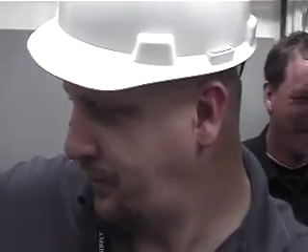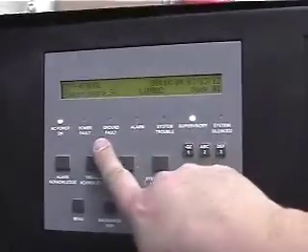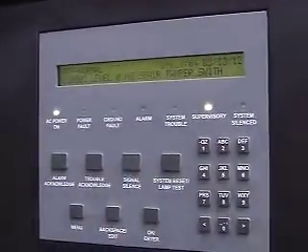But I've seen batteries last 5 years. I've seen them last 10 years. It depends on how much use and how much load gets on them. If you have a lot of power outages, sometimes they tend to start depleting, but it's hard to say when they go bad. It's up to you guys if you have any schedule on your replacement, or if you wait till the panel goes. Some places have a schedule and they go by their schedule, but like I said, when the panel ones go bad, it'll come up and say battery fault on here, so you'll get a power fault that comes up and it'll say battery fault.